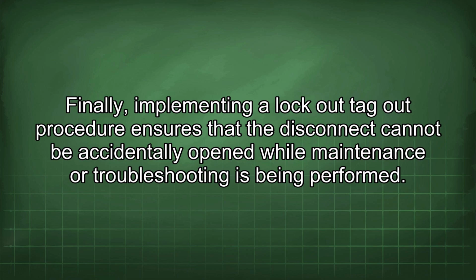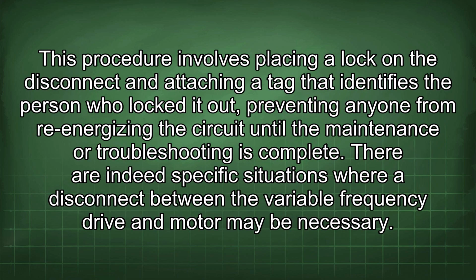Finally, implementing a lockout-tagout procedure ensures that the disconnect cannot be accidentally opened while maintenance or troubleshooting is being performed. This procedure involves placing a lock on the disconnect and attaching a tag that identifies the person who locked it out, preventing anyone from re-energizing the circuit until the maintenance or troubleshooting is complete.